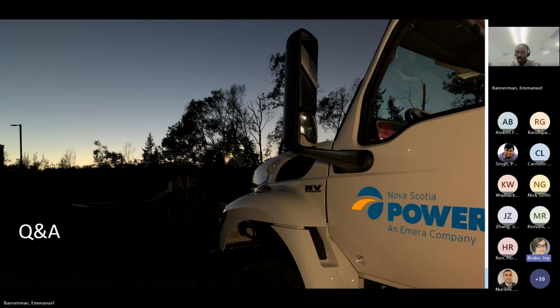And then we say we're going to add this and this and this, and we have to count on that future imaginary system to tell us what we need to do. We can't really benchmark that really super high IBR grid because we're not there yet. So when we match against field data, we're matching our pre-IBR grid. An event where we can get good data has to occur, then we capture the data, then we match it against the PSCAD case. We don't have any of those with very high IBR. We're not there yet.